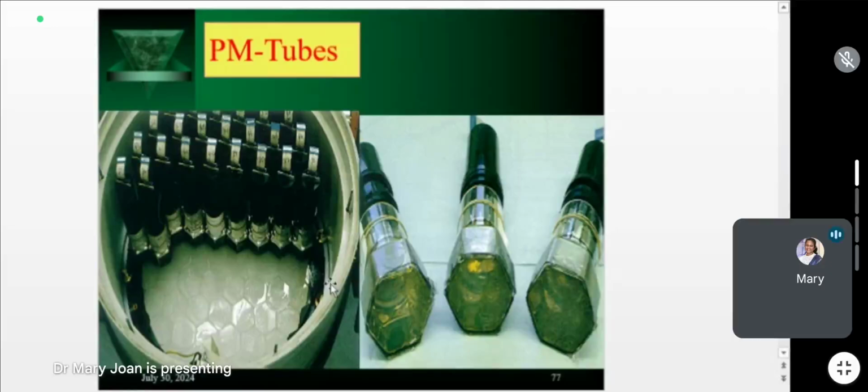So here again the detectors, crystals and the photomultiplier tube. You can see the photomultiplier tube. The sides of the photomultiplier tubes are hexagonal in shape, so that proper stacking of the photomultiplier tubes could be done in the area, so that no light photon emitted by the scintillating crystal is lost.